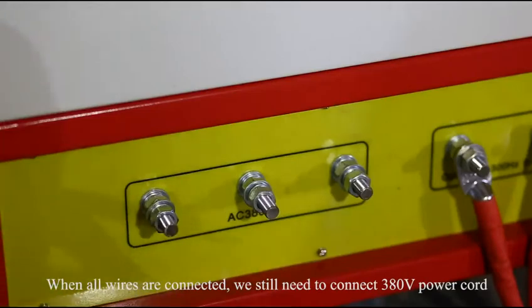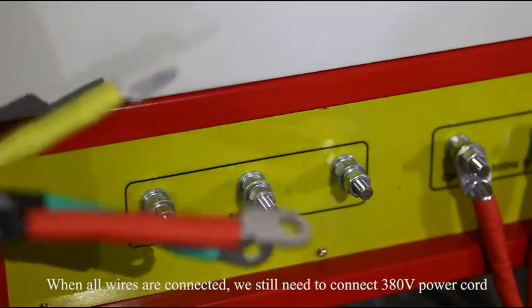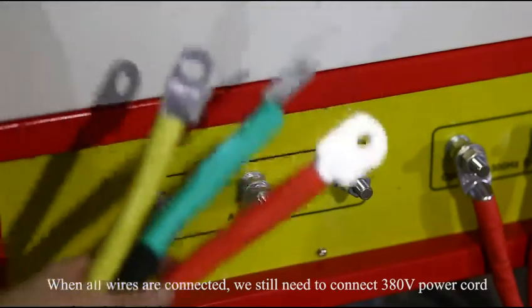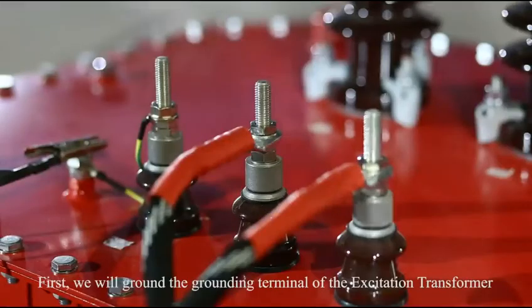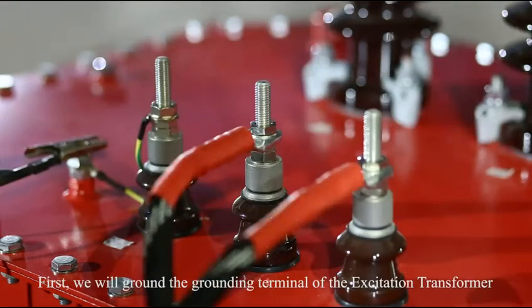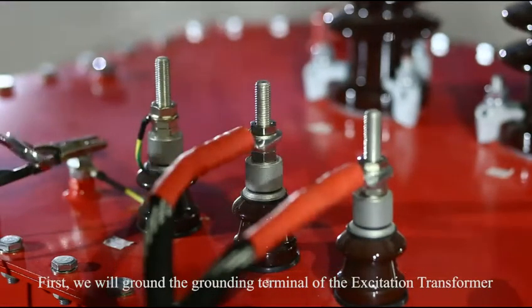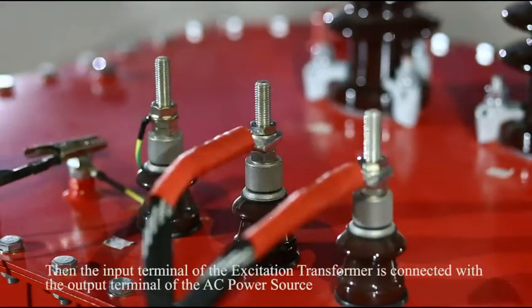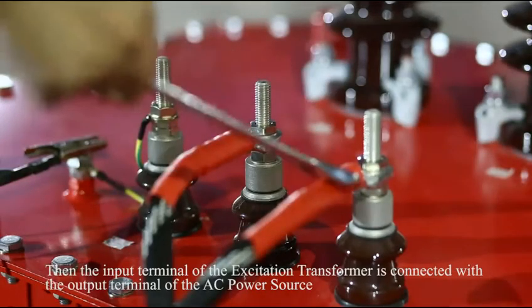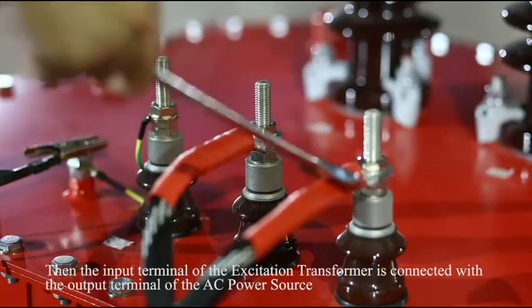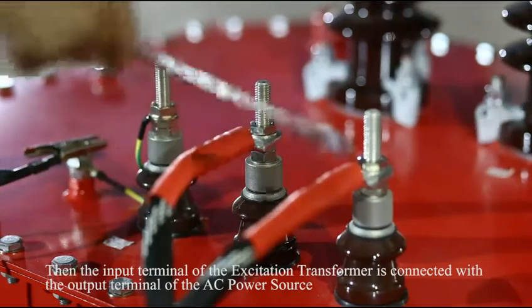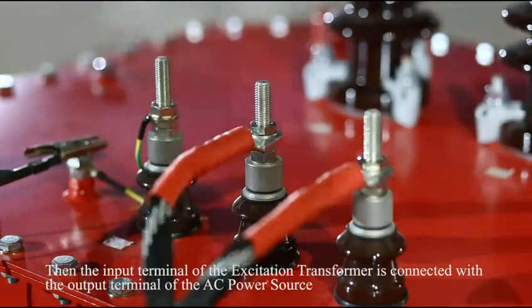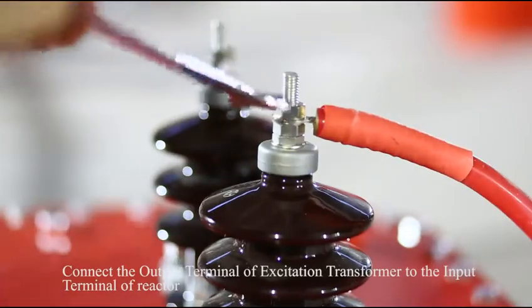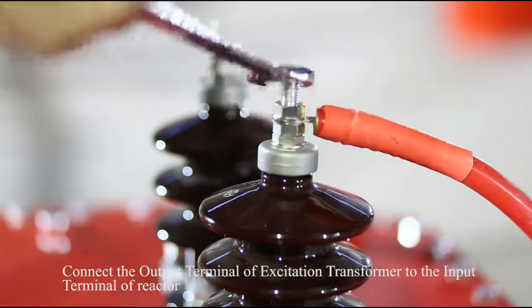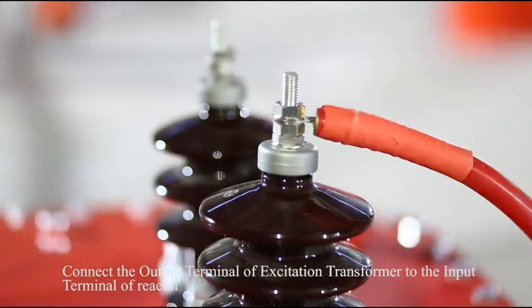When all wires are connected, we still need to connect the 380-volt power cord. First, we will ground the grounding terminal of the excitation transformer. Then, the input terminal of the excitation transformer is connected with the output terminal of the AC power source. Connect the output terminal of the excitation transformer to the input terminal of the reactor.